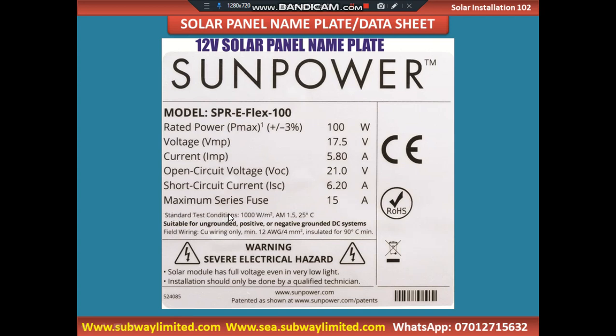Standard test conditions: 1000 W/m², air mass 1.5, 25 degrees Celsius. That was the condition that this solar panel was subjected to. So if you subject this particular solar panel to this condition, you might have a value that is 3% higher than 100 watts or 3% lower than 100 watts.